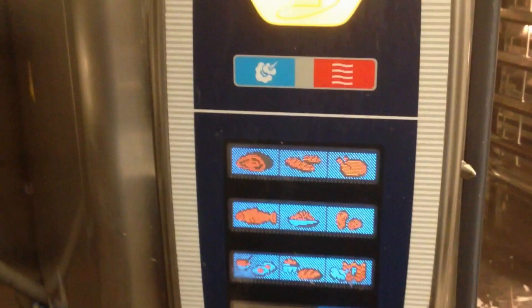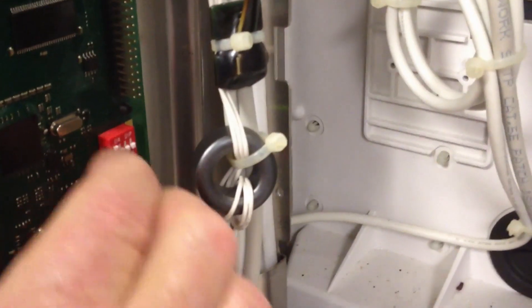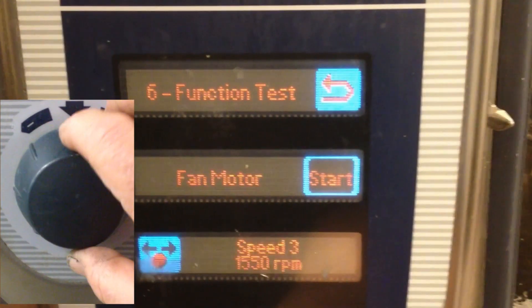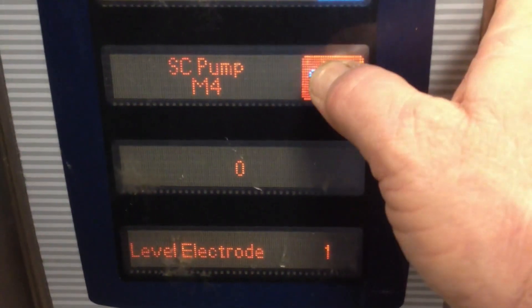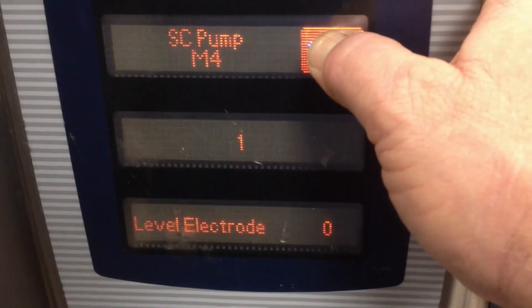At the My Cooking screen, go behind the control panel and turn dip switch number one to the on position. Press the service level key, choose function test, and use the dial to scroll to function test six. The self-cleaning pump is displayed — it's currently off — and the water level electrode displays a one, indicating the water is at the probe. Press and hold the start button and operate the self-cleaning pump until you are satisfied with the results.